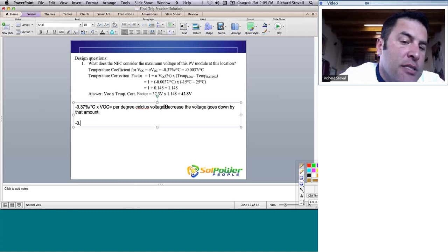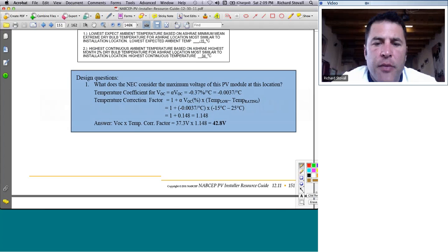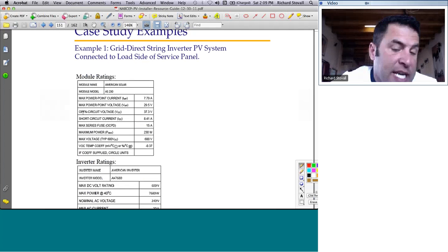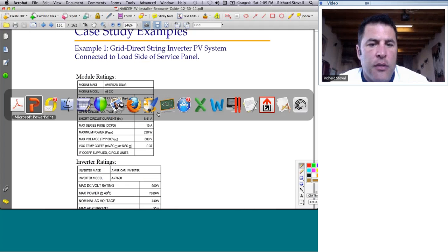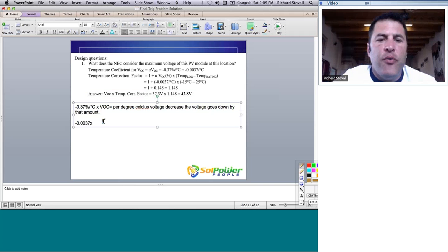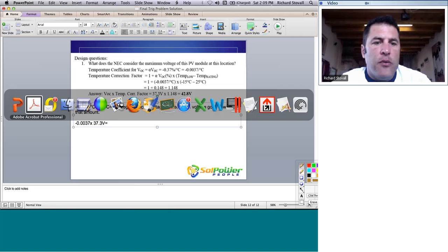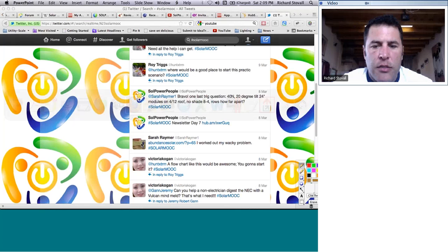0.37% means that you're multiplying 0.0037 times the VOC. And the VOC of this particular module is 37.3, if I recall correctly. Yep. The open circuit voltage under standard test conditions, 37.3 volts. All right?